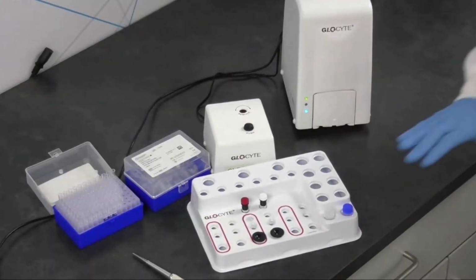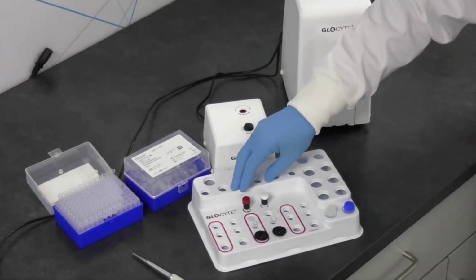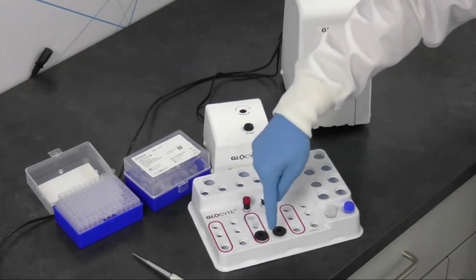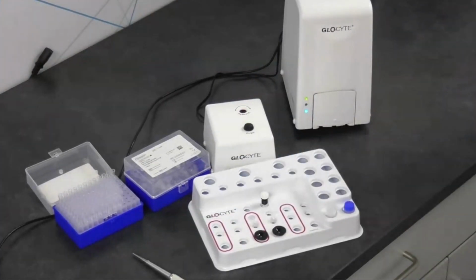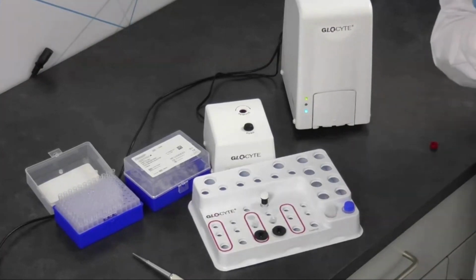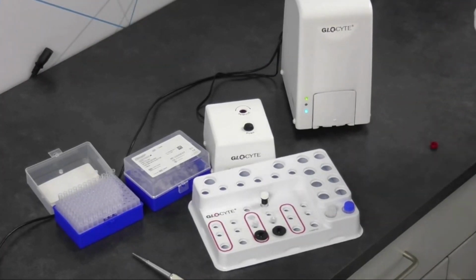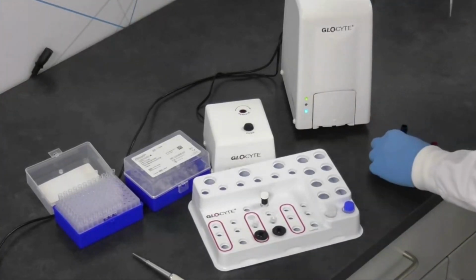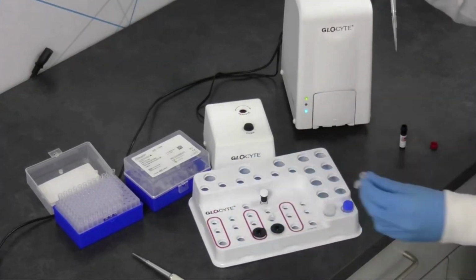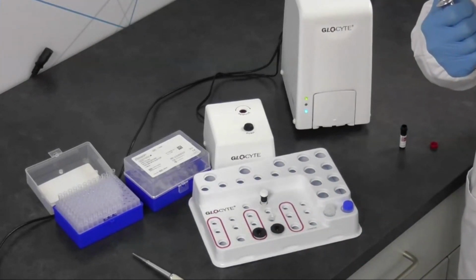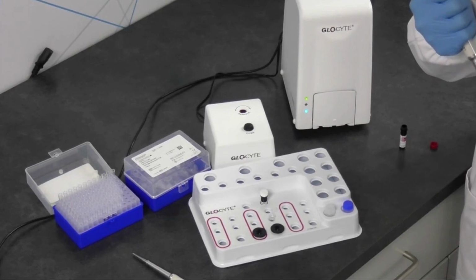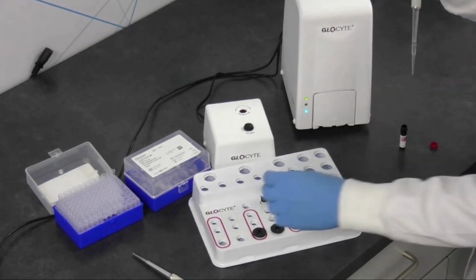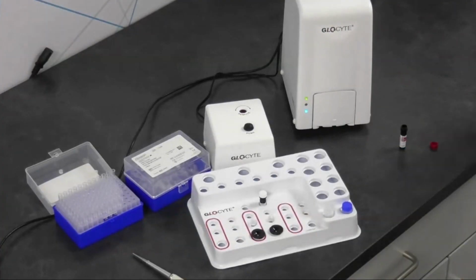Okay, and next, the first thing that we're going to set up is our red blood cell count. So we're going to go over here again to the reagent in front of the red oval, and we're going to open up our red blood cell reagent. And again, we're just going to take up 30 microliters. So pretty simple, no bouncing back and forth between volumes. You just change your tip, go in, add your reagent, and you mix 5 times. Beautiful. And then you're going to close that off and ditch your tip again.